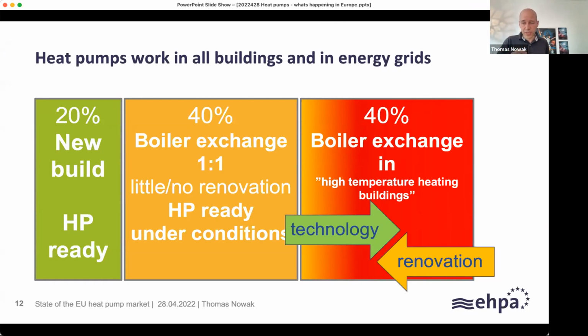Then another 40% we'd say is not fit for purpose immediately, unless we use hybrid heat pumps. You'll hear about this in the Netherlands example - the Dutch government is really betting heavily on hybrid heat pumps. They say if we do that, we can put heat pumps everywhere, because if it's cold in winter and the refrigeration cycle can't do the job, you switch on the gas boiler.